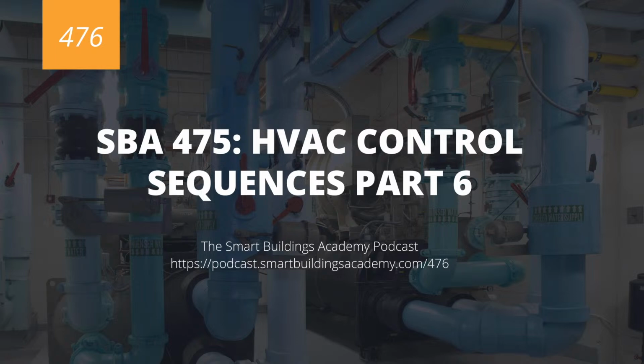Now, as you know, I prefer hardwired. Look, I'm the first person to integrate things. I love integration. It's fun to me. It's exciting. However, when it comes to critical systems and I have an option to hardwire, I'm going to utilize that option. Now, that doesn't mean that you can't have a BACnet card for secondary monitoring. But my primary source of control I like to have be hardwired. I tend to find that from a troubleshooting perspective, as well as from just a peace of mind and stability perspective, hardwired wins the day.